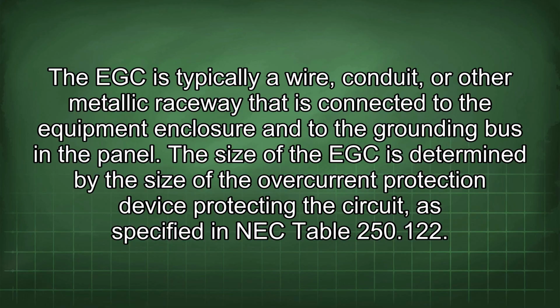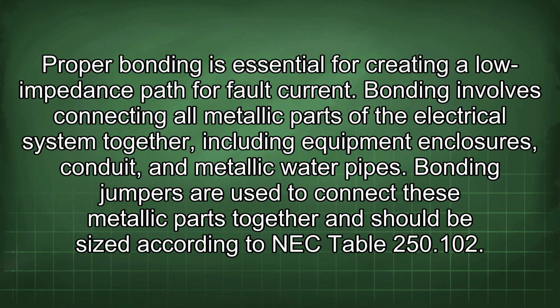The size of the EGC is determined by the size of the overcurrent protection device protecting the circuit, as specified in NEC Table 250.122. Proper bonding is essential for creating a low impedance path for fault current. Bonding involves connecting all metallic parts of the electrical system together, including equipment enclosures, conduit, and metallic water pipes. Bonding jumpers are used to connect these metallic parts together and should be sized according to NEC Table 250.102.